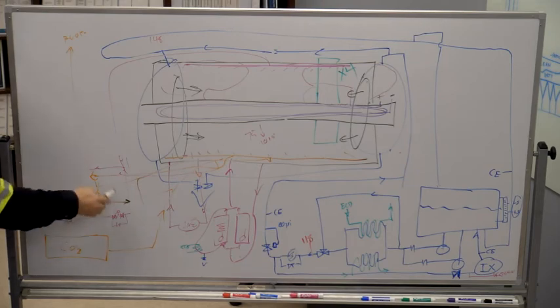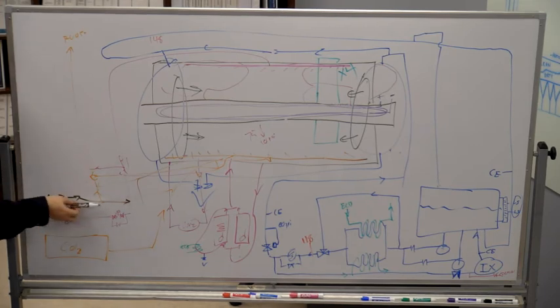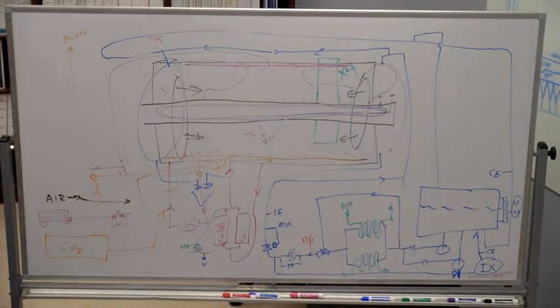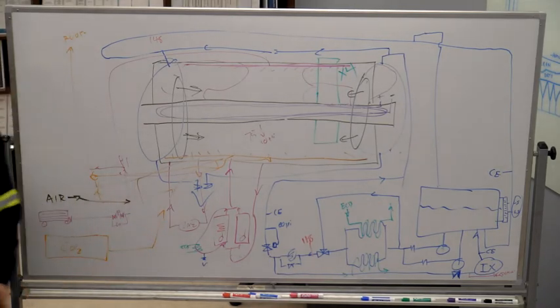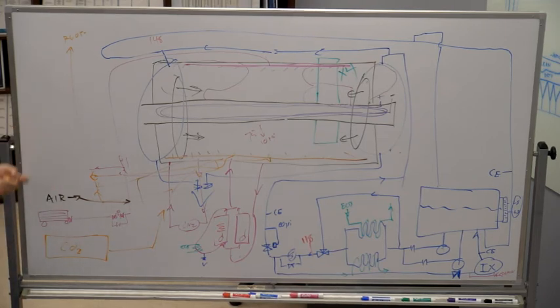And you got to tweak your valves. Try and maintain your pressure. You got a valve on the vent and a valve on the fill. You tweak both of them to try and maintain your 10 pounds, maintain your flow on your analyzer. And then eventually you'll quit reading pure CO2 and start reading air. And then you vent for another four hours. And then you go, okay, she's safe. We can now open this thing up with no worries about explosions.